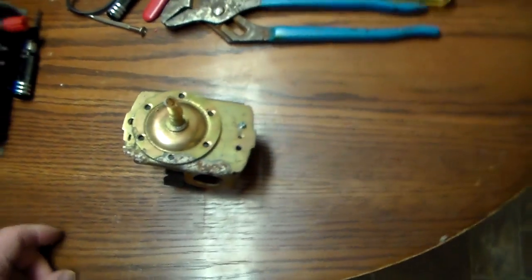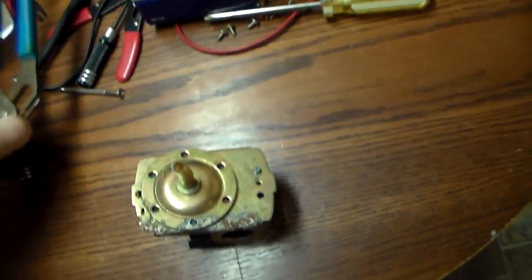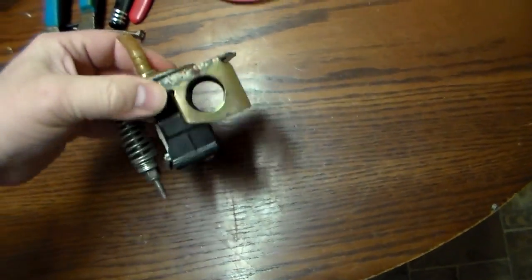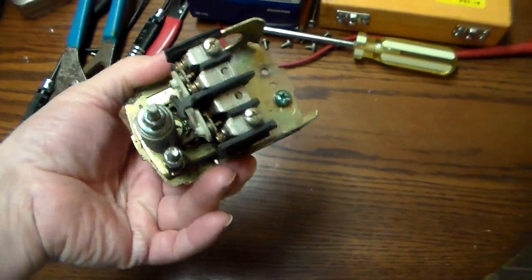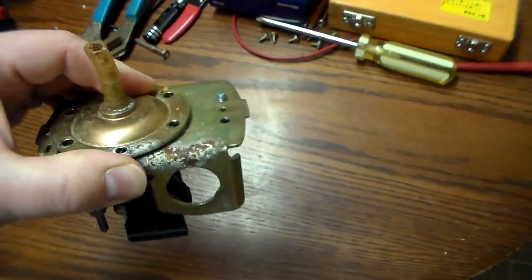Hello there, Roger Foster here. Today we're going to clean up one of these pump controls, the pressure switches for your domestic water pumps. One of the problems that happens is they get a lot of rust accumulation in them.